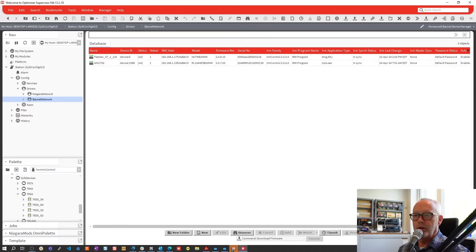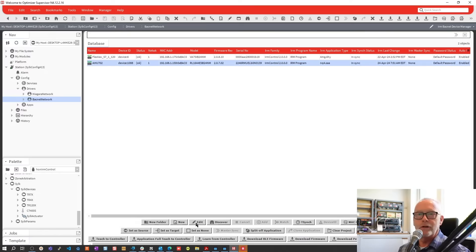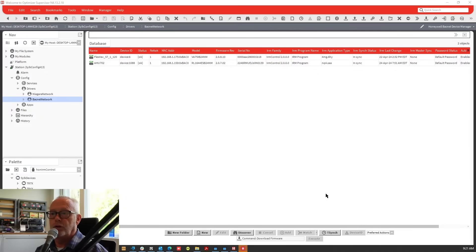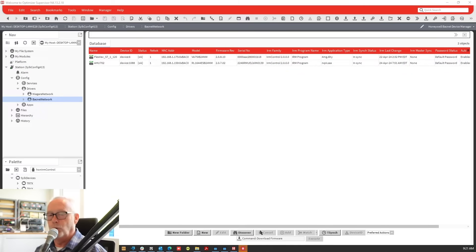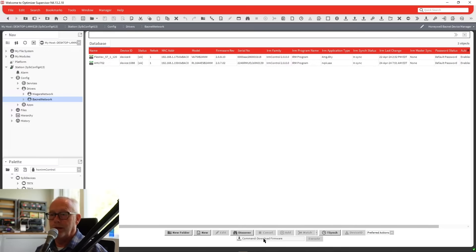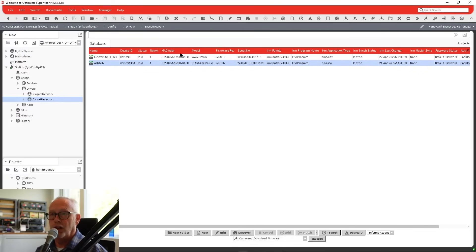When you were in 4.12, you had 33 different buttons to weed through to find the command you're looking for. In the 4.13 Honeywell BACnet device manager view, they've added two pull-down boxes: a command pull-down box and a controller selector. You can select and execute any of the commands available for that type of controller.